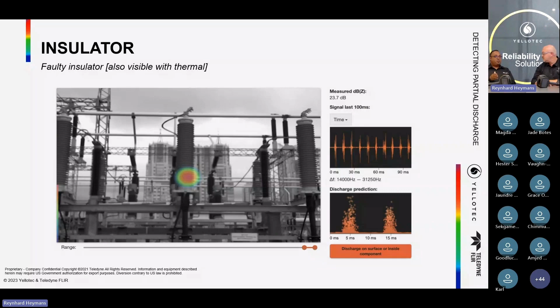Exactly. Right. Here again, you start to look at some of the other examples in open air substations. You've got insulators that could be faulty. Now, a lot of times when you hear this buzz, it's multi-directional. So again, being able to pinpoint exactly where the frequency is coming from is critically important. And the fact that you can see the sound is also important, because now you're able to pinpoint exactly which location you're going to. Excellent. Okay.